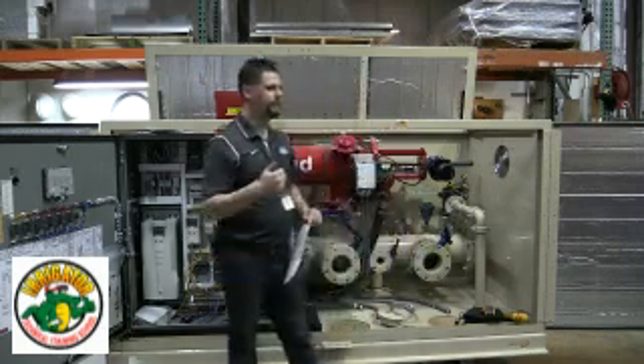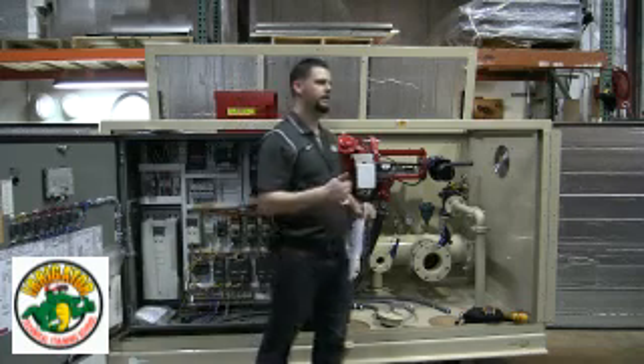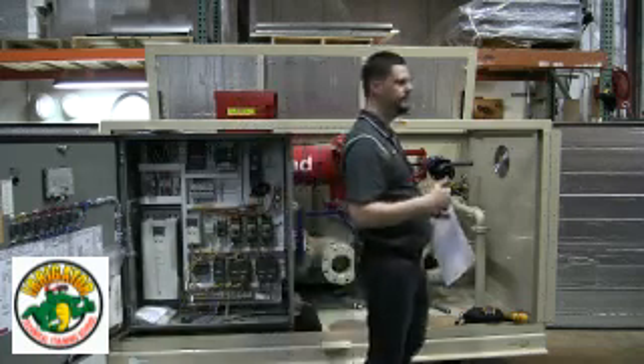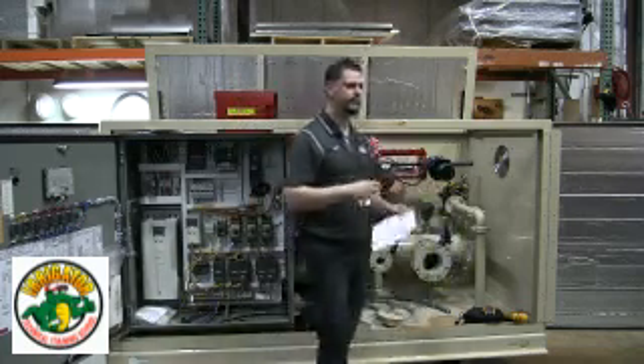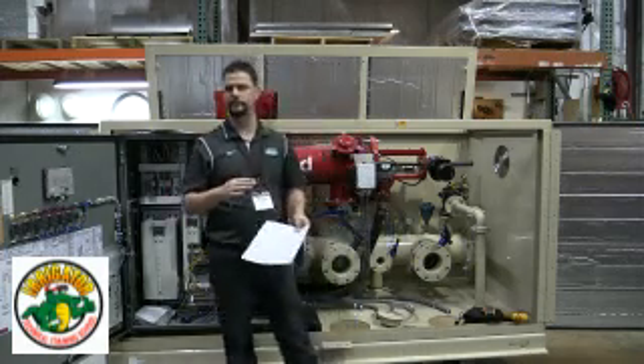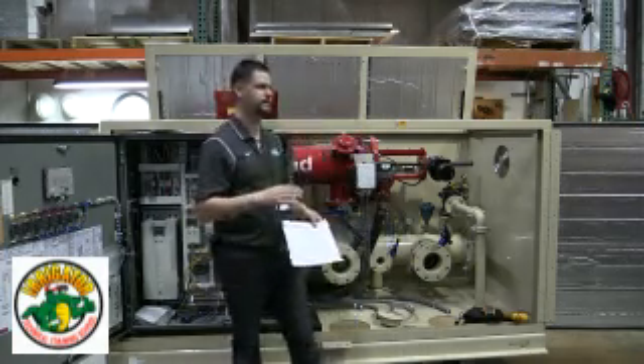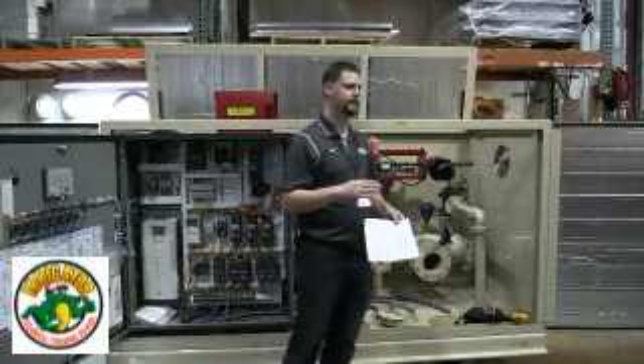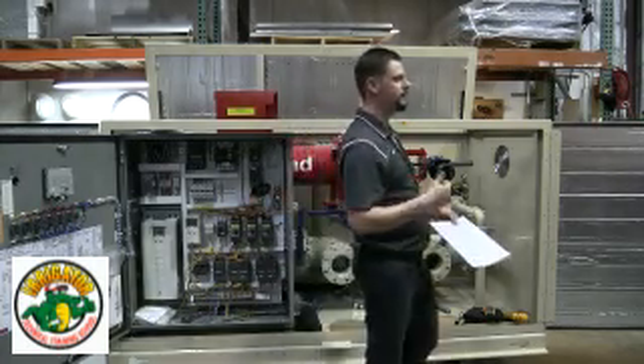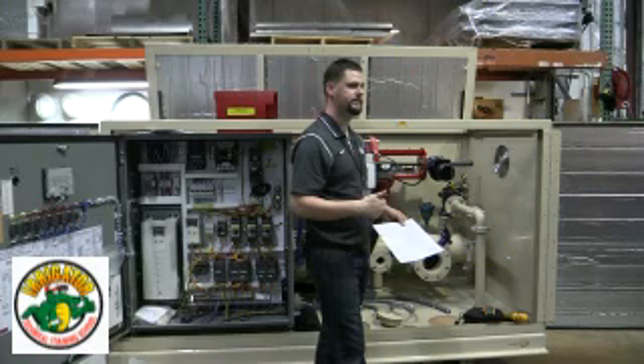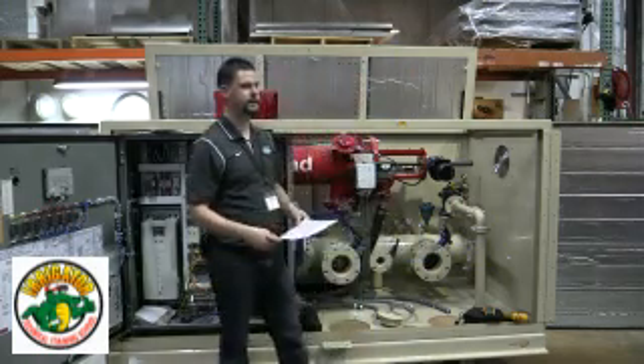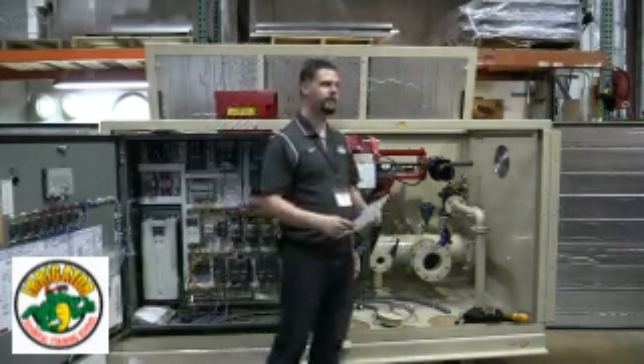Now when we make a pump column, traditionally it's 12 inches from the bottom of the sump, which gives you a full foot of silt before you're going to have problems. Usually I alert the customer when they're at 6 inches or more. If they're above a foot, I will not run their pump station.